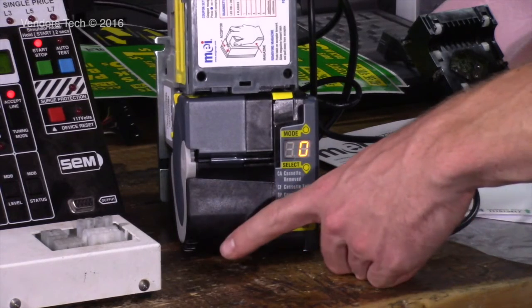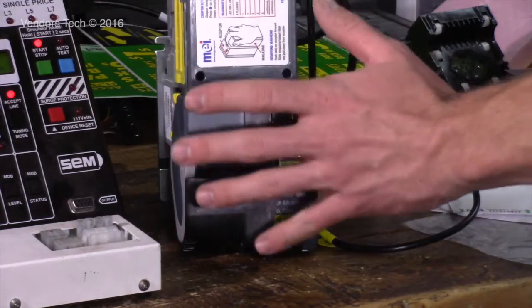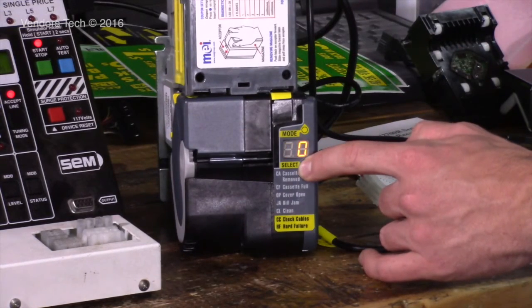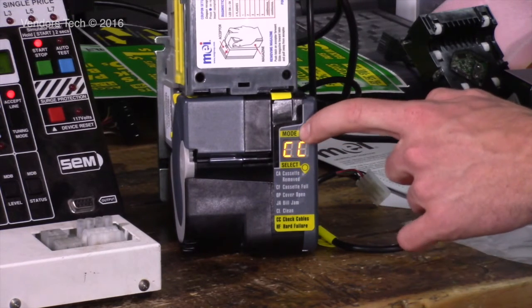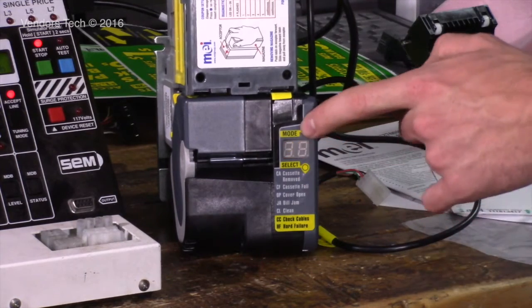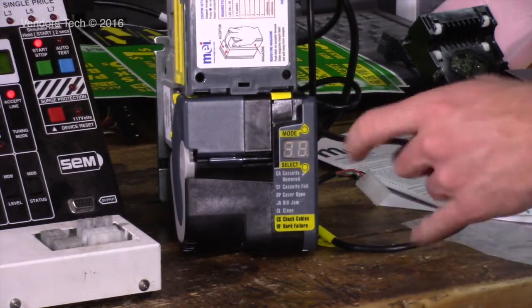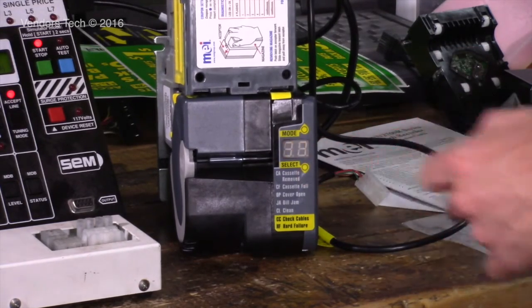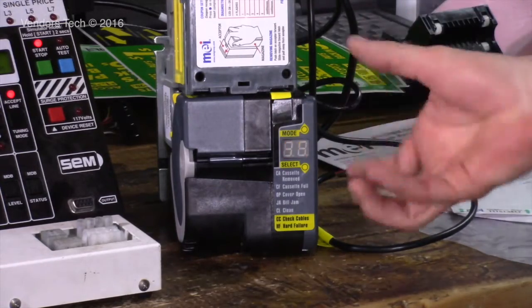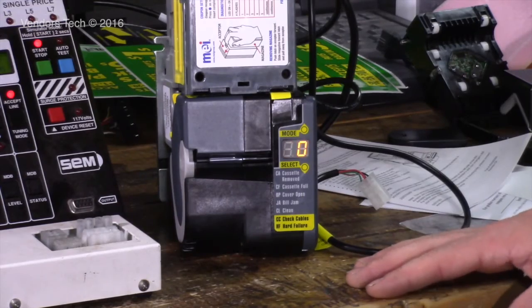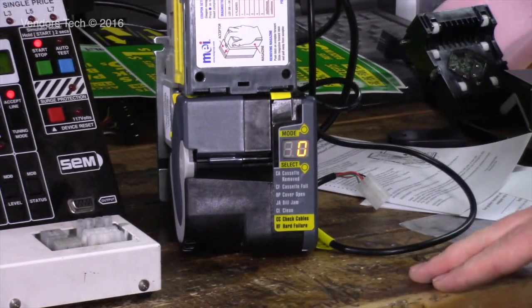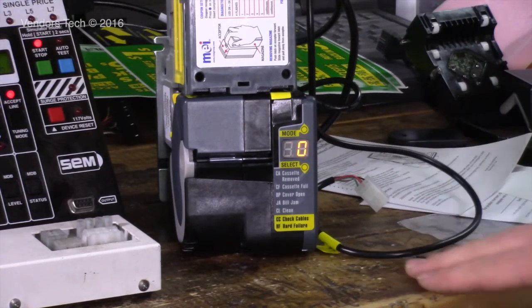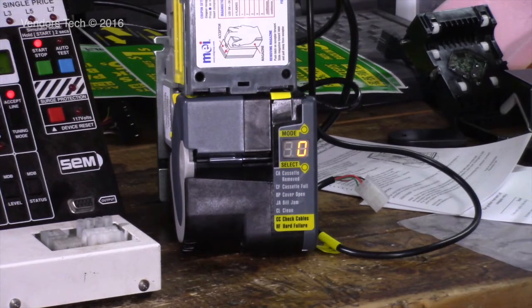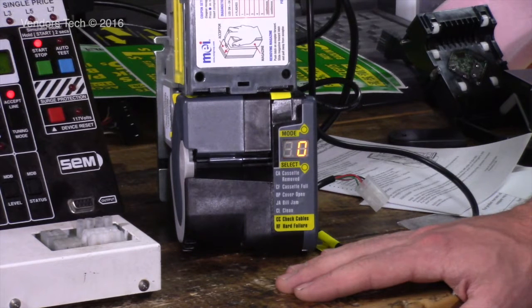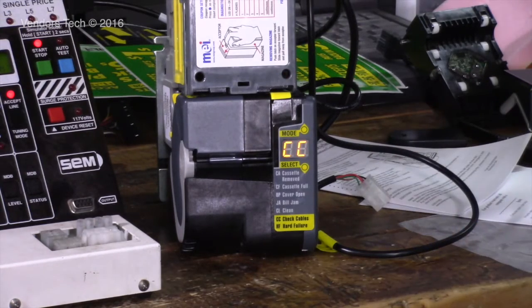I also like to calibrate the film inside of your recycler, and you do that in the same menu area. So we're going to hold down select till it flashes, hold down mode, LD, SU, enter mode. We're going to go to PR, select. It says CL. We're going to hit mode again. It's going to say F1. Hit select. Now it's calibrating the film inside of the recycler. This process takes a minute or two. It rolls it all the way one way and rolls it all the way the other way. I like to do it in the beginning. I'm assuming they calibrate these things at the factory. You don't have to do it, but all right, and it's calibrated and ready to go.